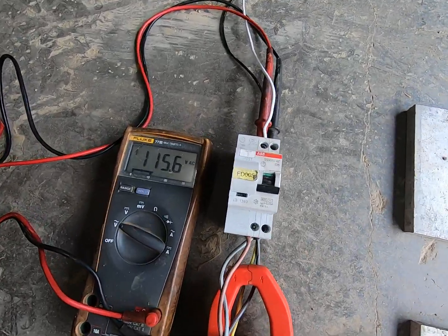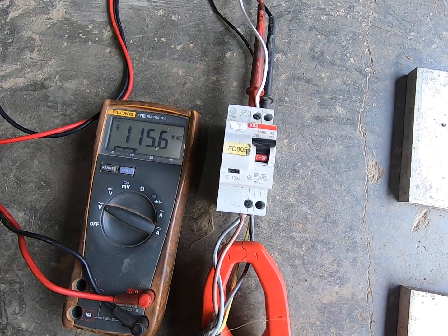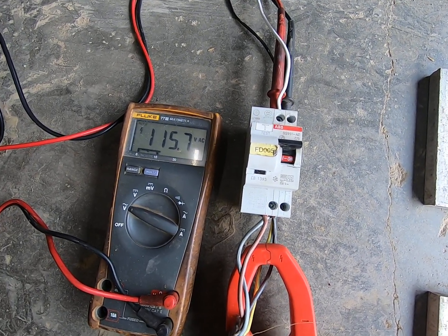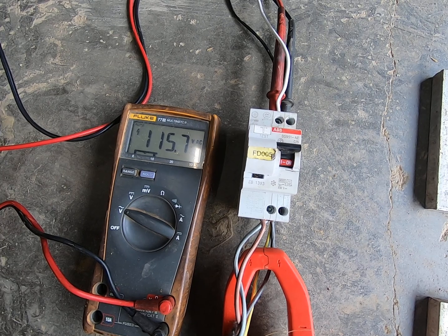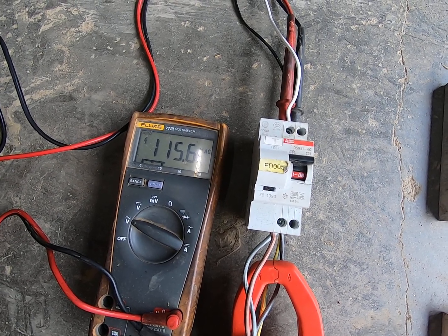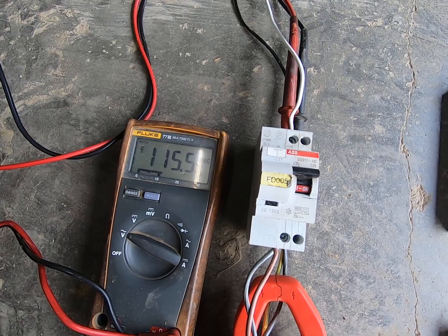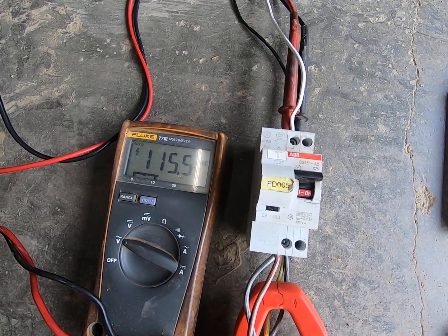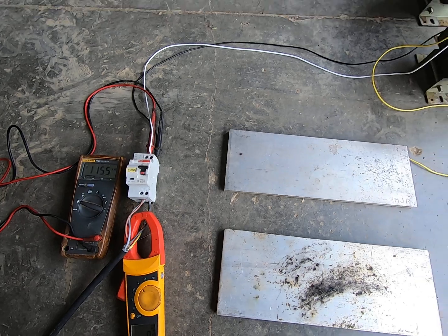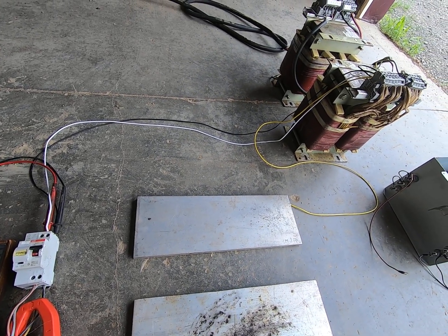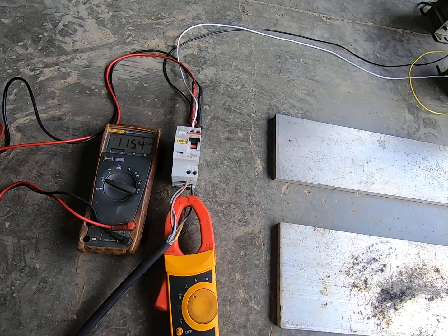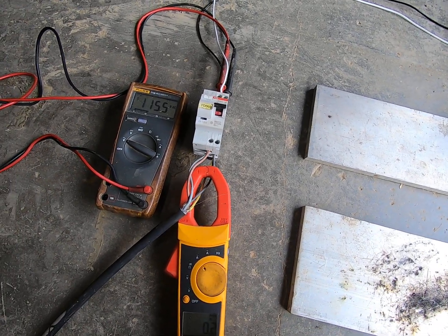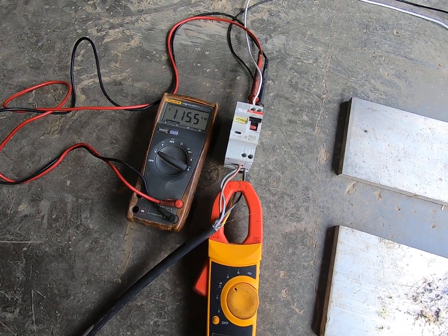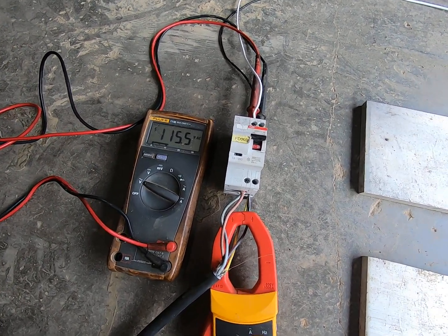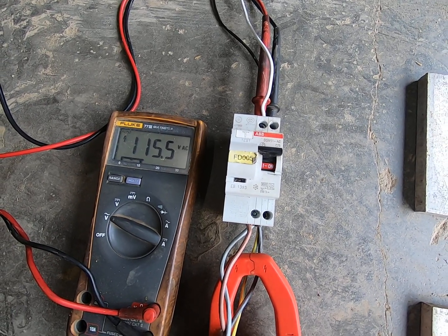Now this particular breaker has a fuse curve called a C fuse curve, which means the instantaneous trip is anywhere between 5 and 10 times the circuit breaker rating. So instantaneous means obviously it would trip right away. I can only get about 70 amps, primarily due to the transformer that's being used and the length of cable. I get such a big voltage drop that the amount of current is limited.